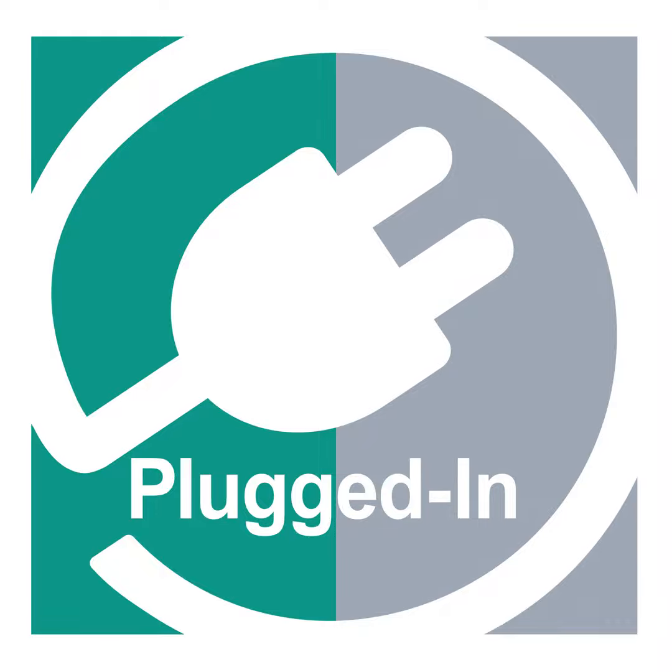Okay, at this point, I think we need to talk about what it means to be safety-ready. Can you give us some details and some examples? Yeah, so by being safety-ready, this encoder has what we call diverse redundancy, which means that there's basically two encoders in the same housing. We have an optical encoder and a magnetic encoder, so you have two separate outputs. And the reason for this diverse redundancy is so that you won't have a common mode failure.